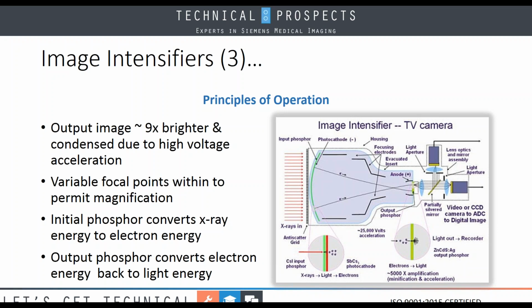input. The phosphor here, again, we said it converts the X-ray to electron energy, and the output converts the electron energy back to light energy. From there, we have our mirror optics assemblies, where we can direct the light coming off of the image intensifier to different devices, whether it's a video camera, CCD camera, a video tube. We can direct it off to different other cameras, and we do a lot of different things with that image coming off of the intensifier.